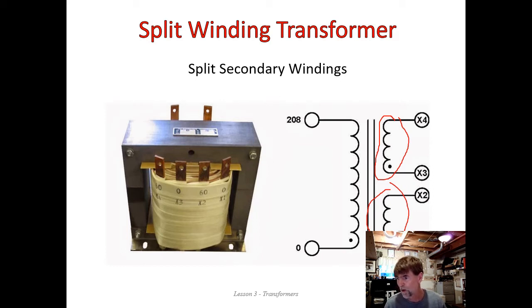Okay. Now the drawing shows the 2 secondary coils side by side. The fact of the matter is, in terms of the actual construction, these 2 coils are wound together. If you look at this, you can see that this is a shell type core. And so we know in a shell type core that the low voltage winding is wound around that inner core piece, and then the high voltage winding is wound around it. So we've already got the 2 windings, the primary and the secondary winding, trying to occupy the same space. The 2 secondary windings are in a similar fashion. They're occupying the same space. They're not side by side the way the drawing shows it. They're actually wound around each other in addition to the primary, so everything's kind of all crammed in there together.